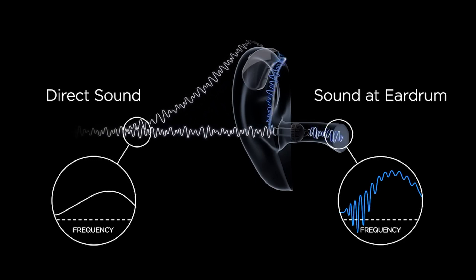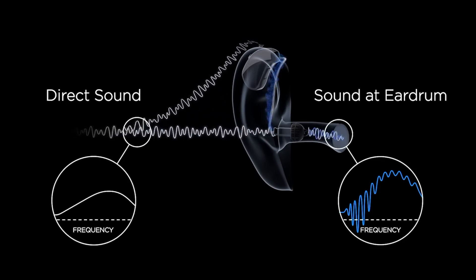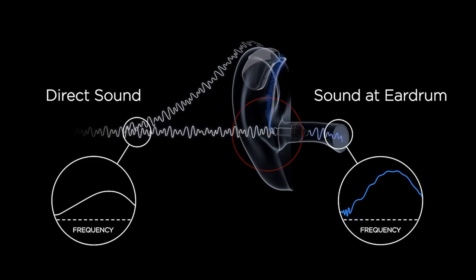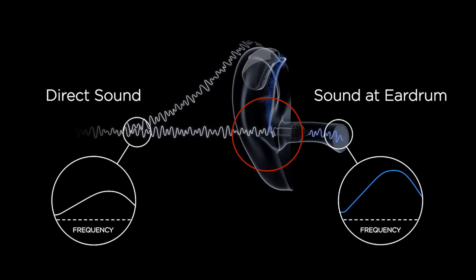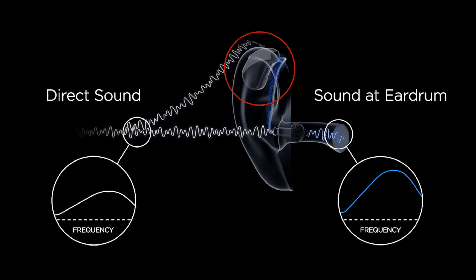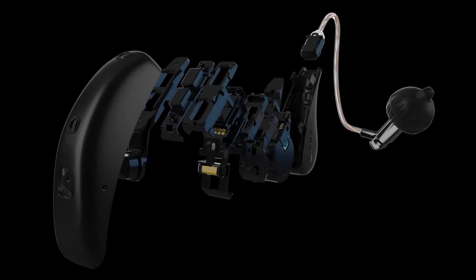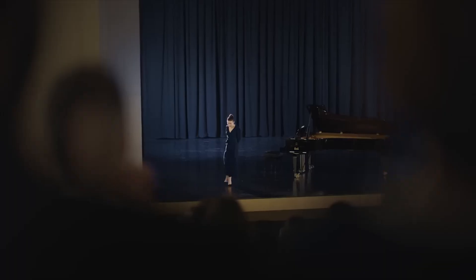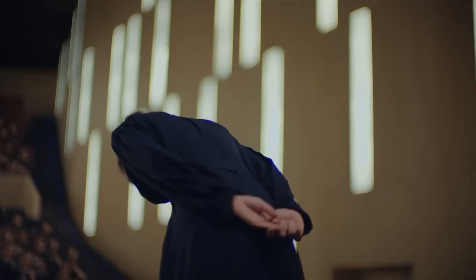What this does is actually reduce the comb filter effect, which is an artifact introduced into a signal when you have some natural sound entering your ear canal unaffected and then combining with the amplified sound coming in from the hearing aid. Widex also has a very good sound classifier system that can identify what type of acoustic environment you're in and switch your program settings to be more ideal for those environments.